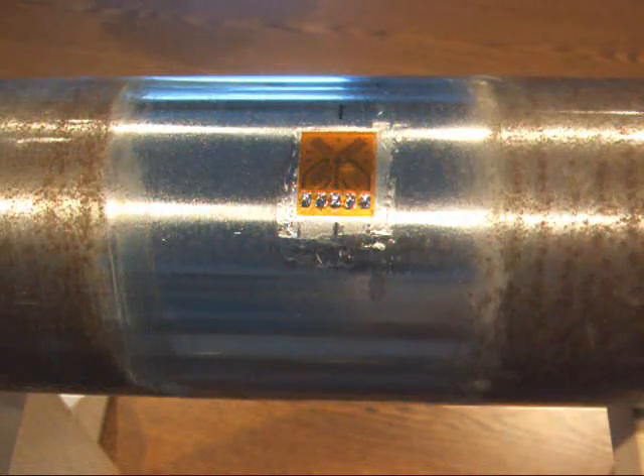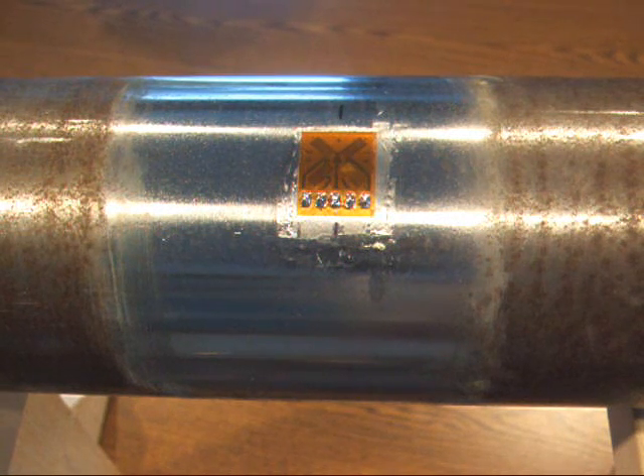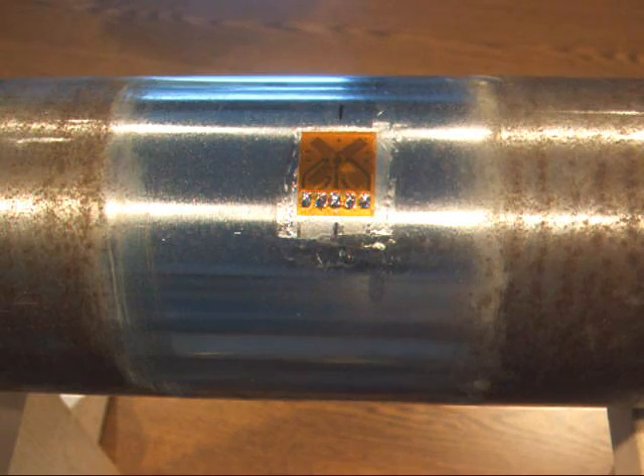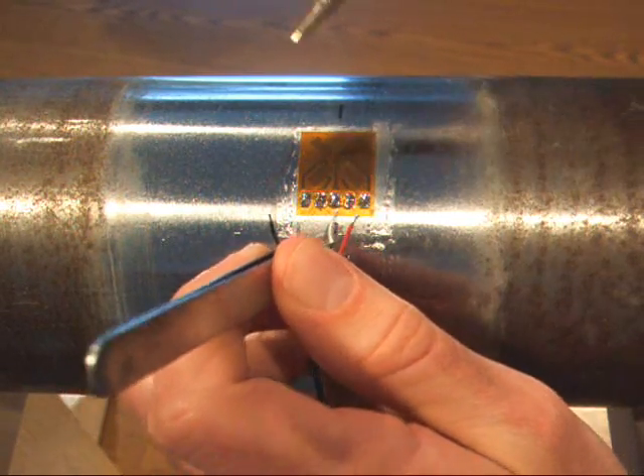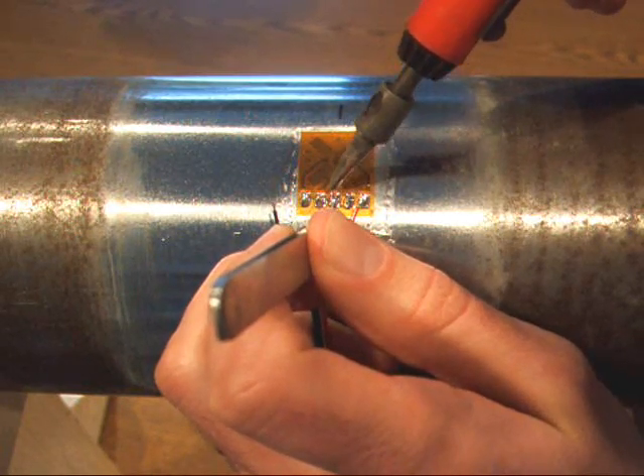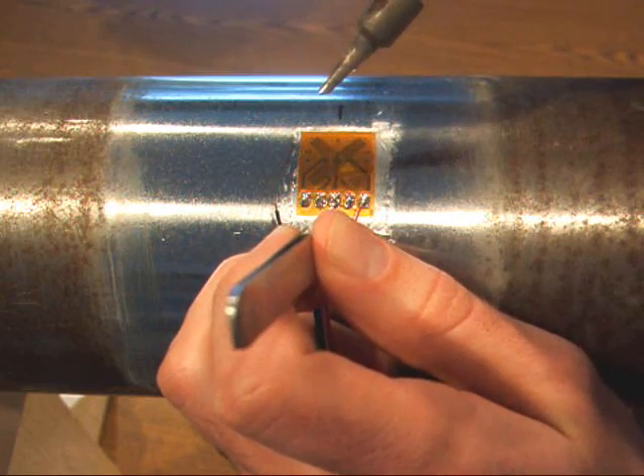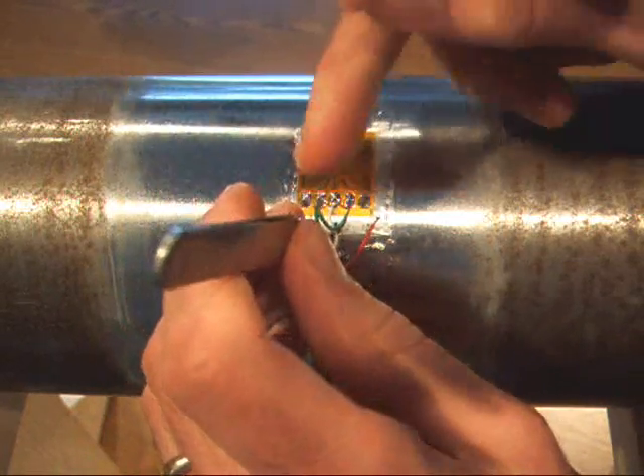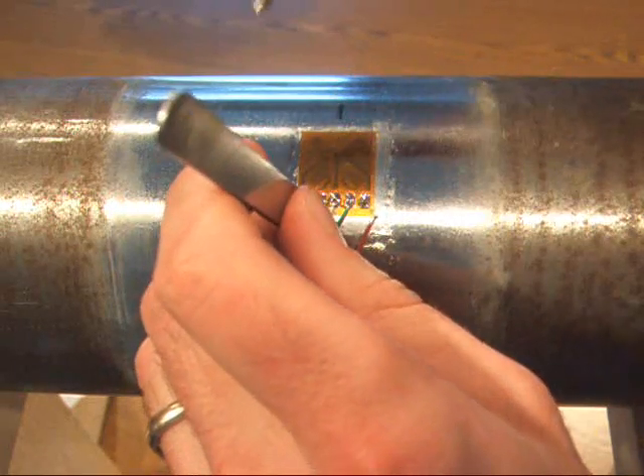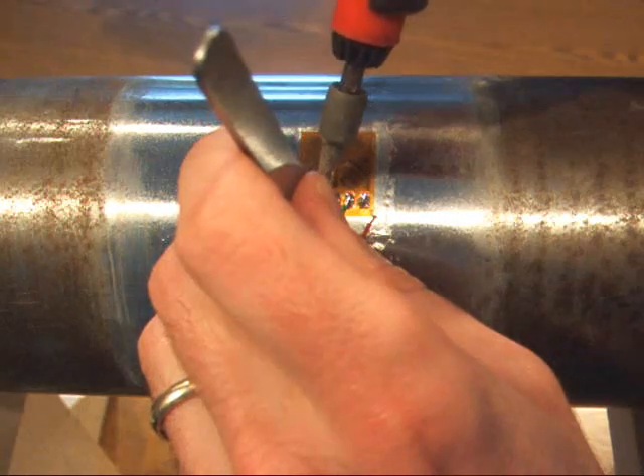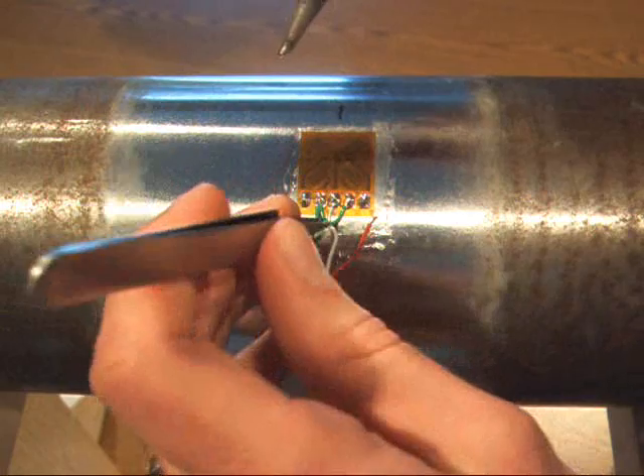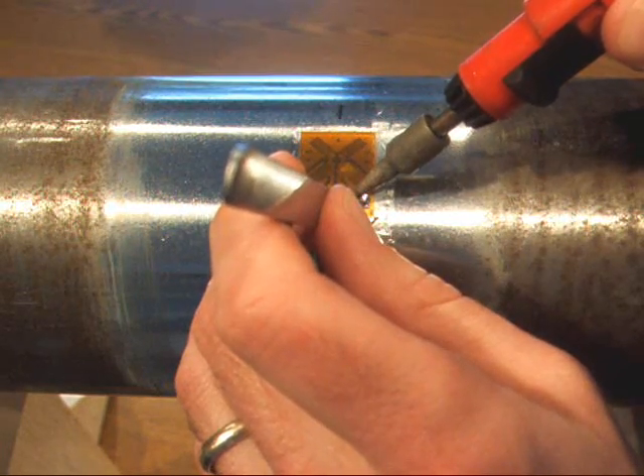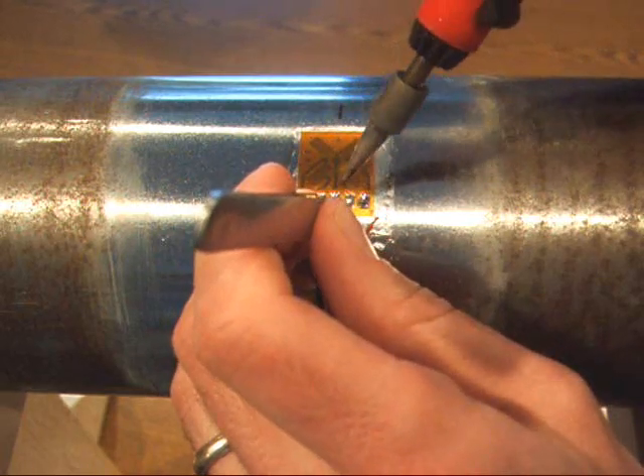Now I'm ready to solder my lead wires to the strain gauge. I'm going to use the tweezers to attach the wires. They allow me to hold them in place without damaging the wire or burning my fingers. As you can see, these wires are quite small. And I'm working from the inside towards the outside. The reason for that is that sometimes it can be difficult to solder the inner lead wires once the outer lead wires have been attached.